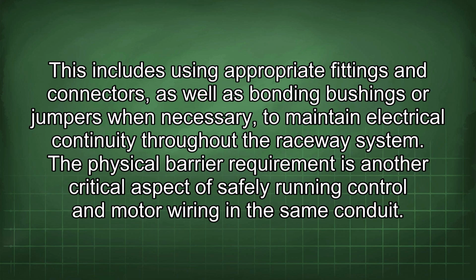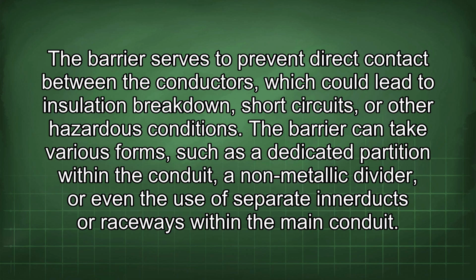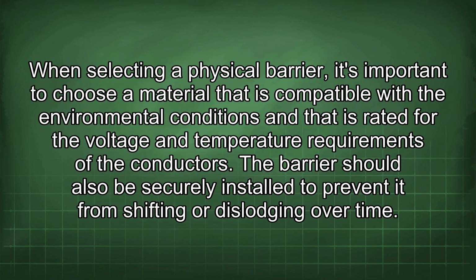The physical barrier requirement is another critical aspect of safely running control and motor wiring in the same conduit. The barrier serves to prevent direct contact between the conductors, which could lead to insulation breakdown, short circuits, or other hazardous conditions. The barrier can take various forms, such as a dedicated partition within the conduit, a non-metallic divider, or even the use of separate innerducts or raceways within the main conduit. When selecting a physical barrier, it's important to choose a material that is compatible with the environmental conditions and that is rated for the voltage and temperature requirements of the conductors. The barrier should also be securely installed to prevent it from shifting or dislodging over time.